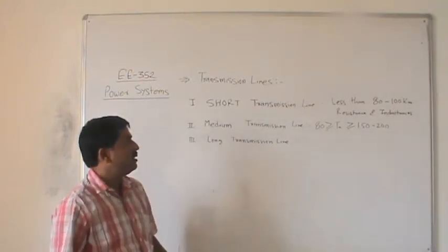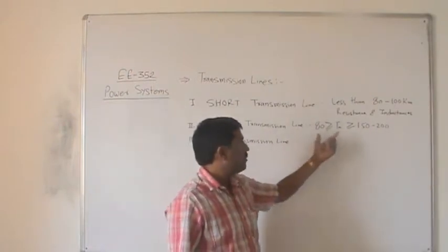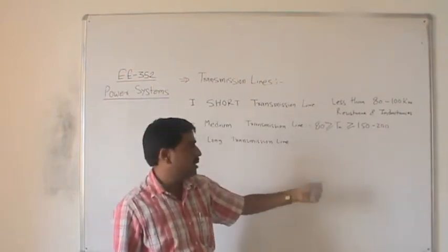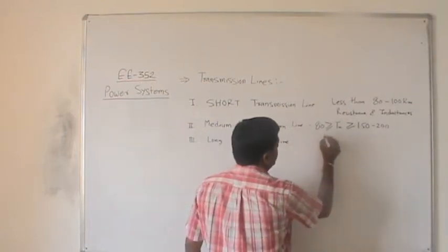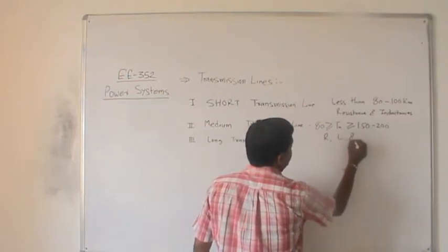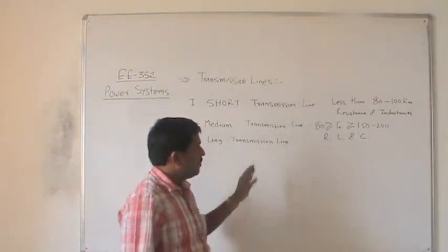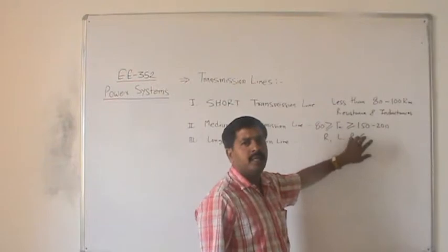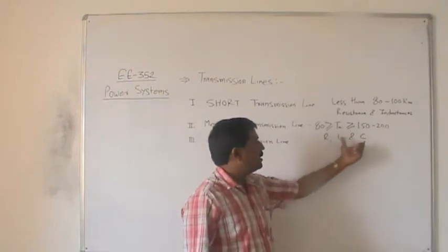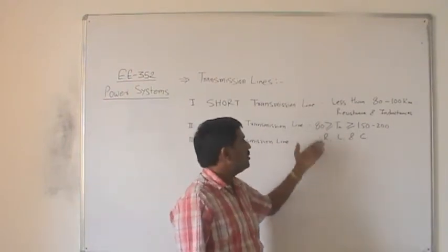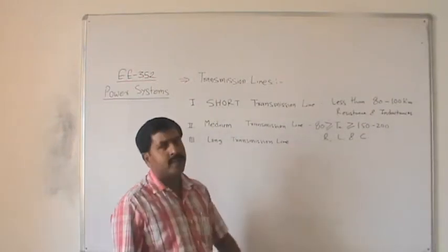For the medium transmission line, the length lies between 80 to 150 or 200 km. For analysis of this type, we consider resistance, inductance, and capacitance. Here we take the capacitor as a lumped parameter, because the line length is not long enough to treat it as distributed.